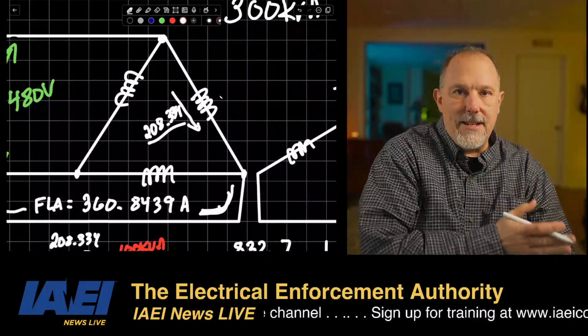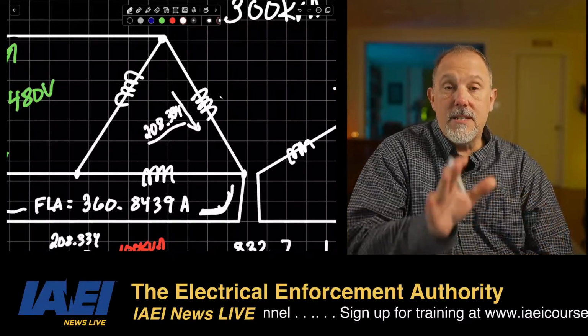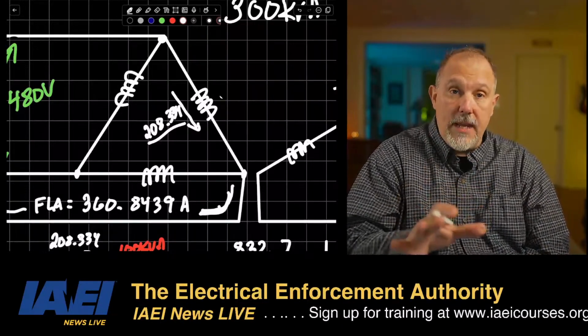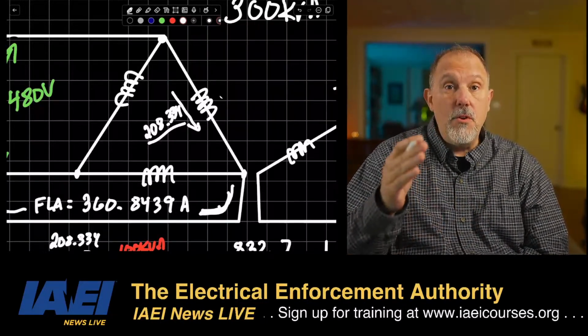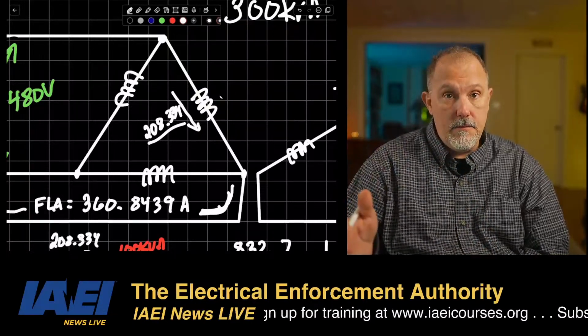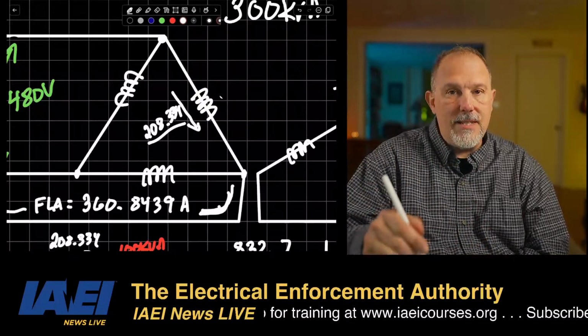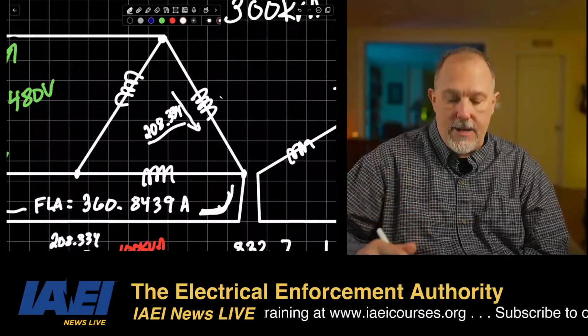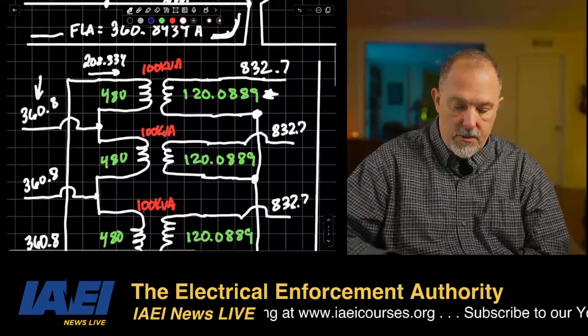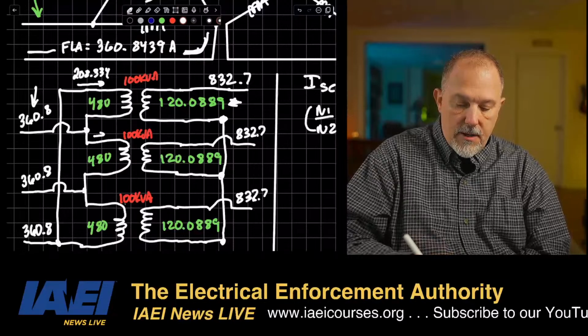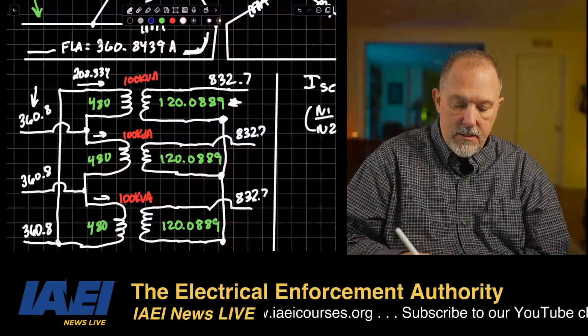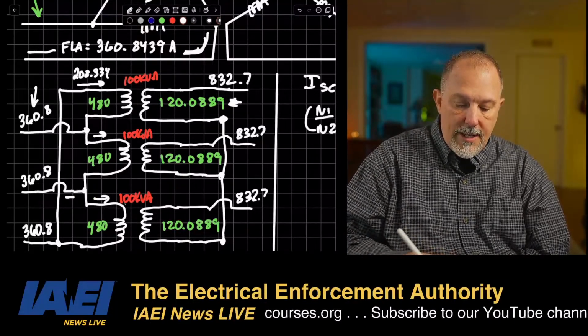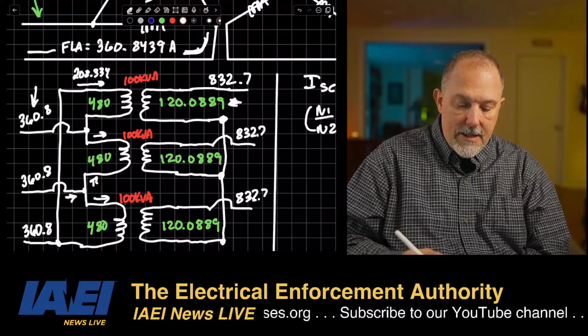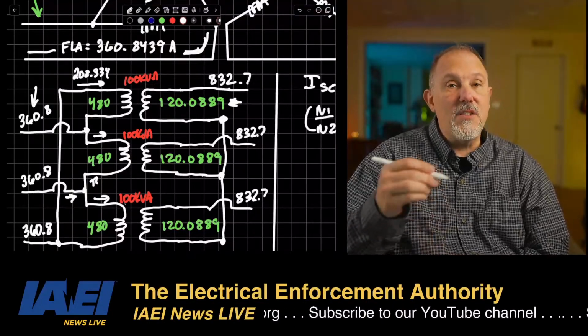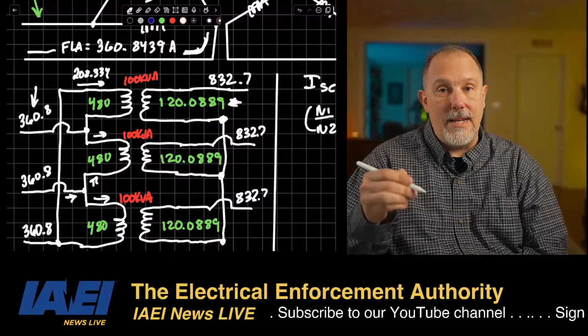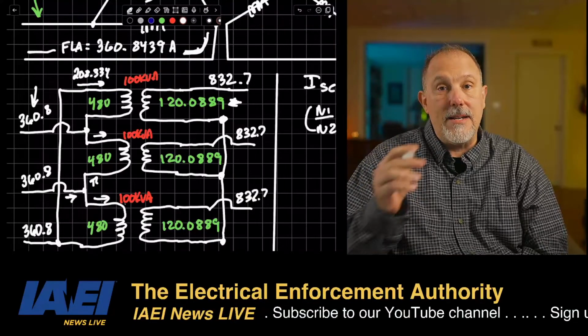I'm not outside of the delta. This is a mistake you may make if you use the 480 to 120. You're only calculating what's in the delta on the primary of every one of these transformers. Every one of these transformers has that same current. But what's flowing here is not the current that's flowing through the primary winding because I'm in delta.